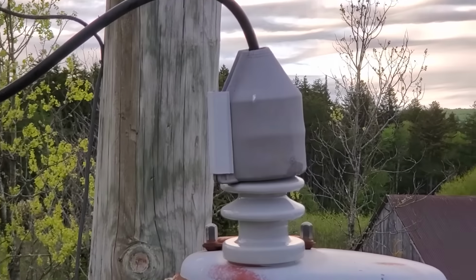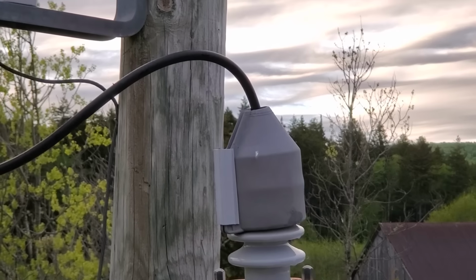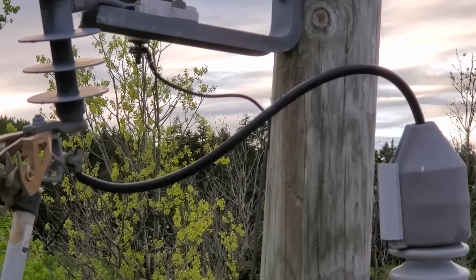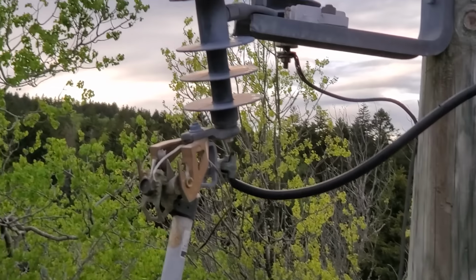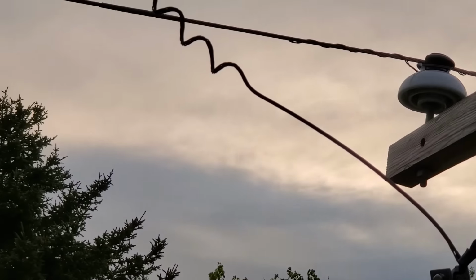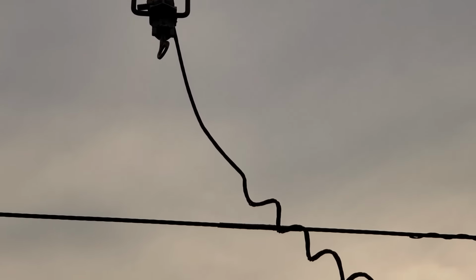So we put that squirrel guard on there, as well as we use an insulated wire with very thick insulation going from the bushing to the cutout and then back to our bare copper as it goes up to the top clamp and the stirrup on the overhead primary.